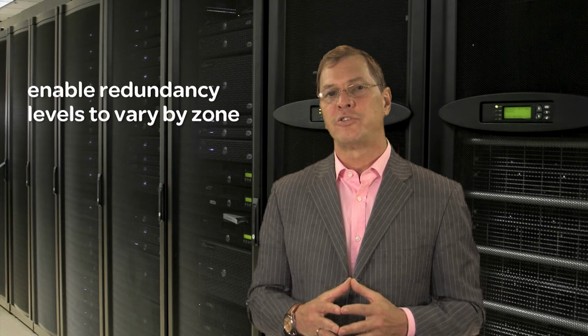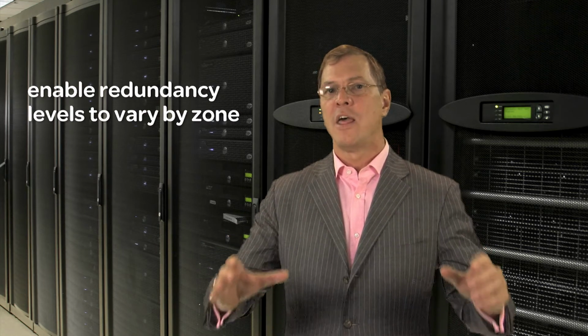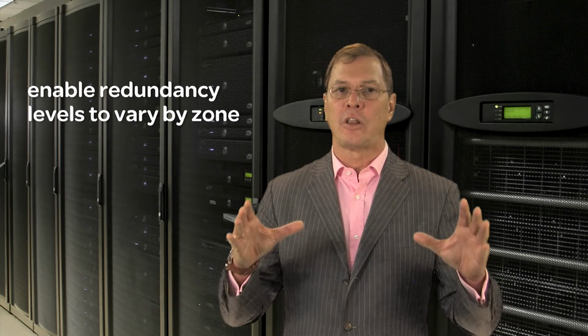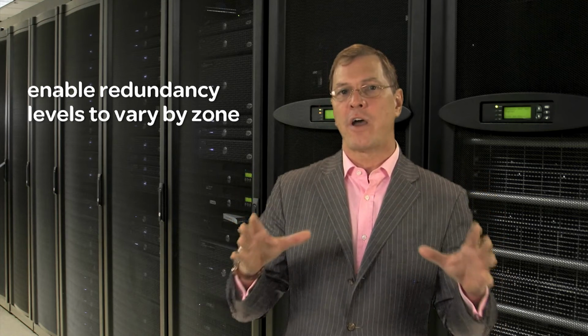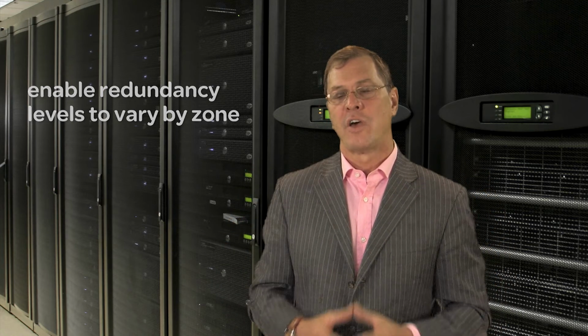And finally, we should think about designing the data center in terms of zones, and the architecture should support a zone-type deployment that allows us to have the physical systems have different availability requirements in different zones. For example, today, if I build a data center, I pretty much have built it to one tier level across the entire facility. But if I build it in a modular zone fashion, it's possible to consider a data center where in the future a new zone might be deployed at a different availability level than a previous zone.